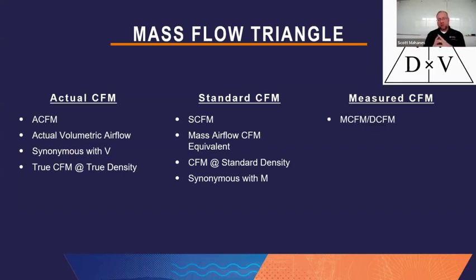The third type that I want to talk about briefly, I don't want to spend a lot on this, is the MCFM or DCFM value, digital or displayed or measured CFM value. And what I'm talking about with this is our instrumentation, our tools that we use are very different. We have rotating vane anemometers, we have digital micromanometers, we have hot wire anemometers, and sometimes our tools don't do full compensation. If I have a DMM that doesn't have a temperature probe with it, it's going to do a barometric pressure auto correction, but it doesn't do it for temperature. And so as a test and balance professional, I have to be sure that if I'm using a DMM without a temperature probe and I'm measuring something other than 70 degrees, I need to compensate for that measurement.